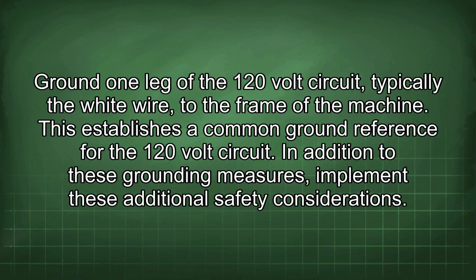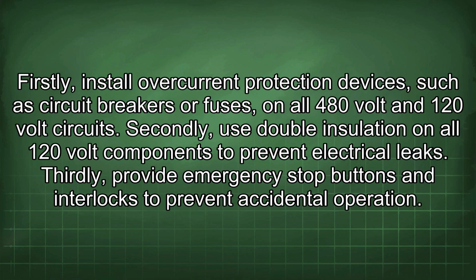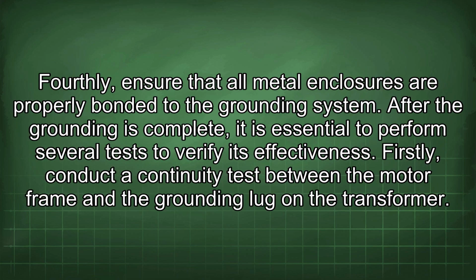In addition to these grounding measures, implement these additional safety considerations. Firstly, install overcurrent protection devices, such as circuit breakers or fuses, on all 480-volt and 120-volt circuits. Secondly, use double insulation on all 120-volt components to prevent electrical leaks. Thirdly, provide emergency stop buttons and interlocks to prevent accidental operation. Fourthly, ensure that all metal enclosures are properly bonded to the grounding system.